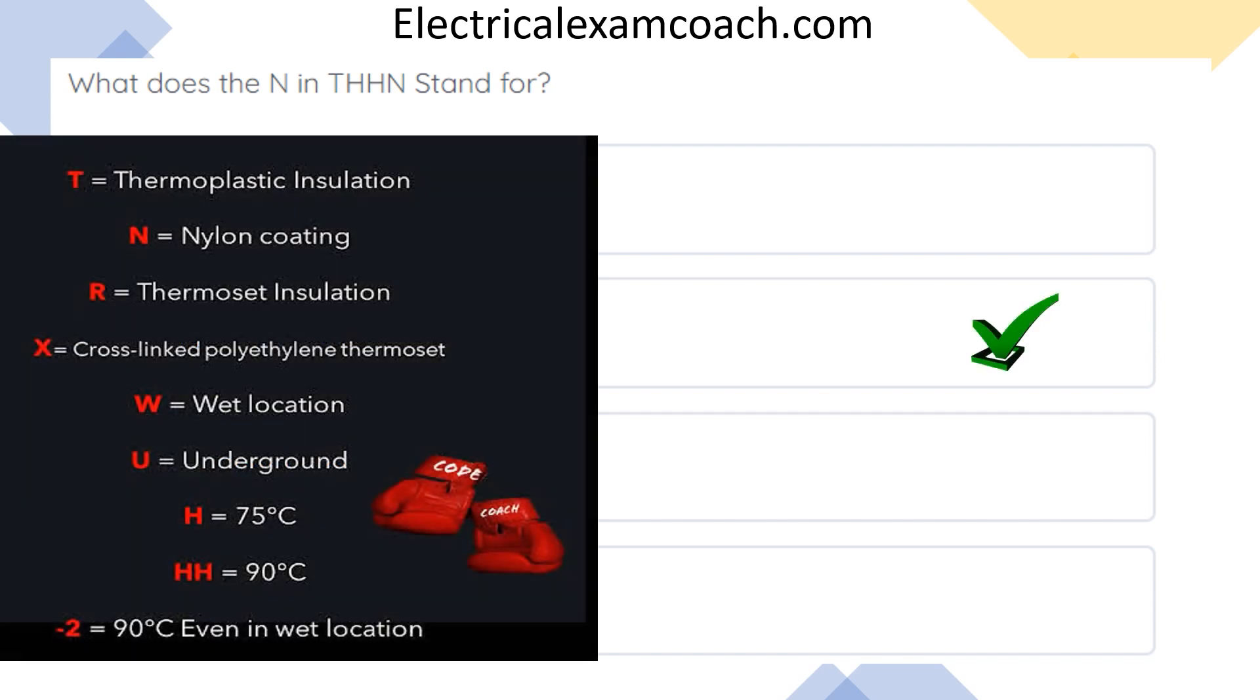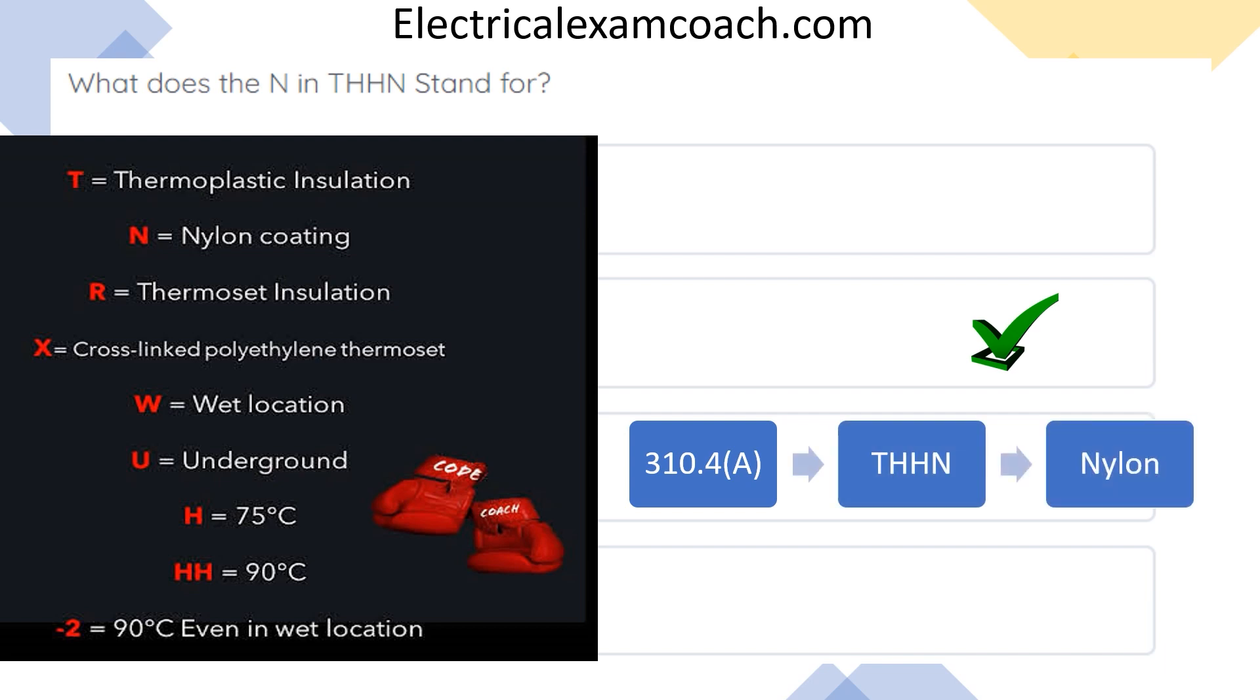So this is a picture that you can get at electricalcodecoach.com under free resources. And this is something that you can use to help you remember. This breaks them all down. How to find it in the code book is something that I actually want you to make a tab for. If you're allowed to make tabs in your state, if not, I just want you to go get familiar with the table. So you're going to head to table 310.4a and you're going to find THHN and then you would be able to find that it is equivalent to nylon coating. And when you get in there, you're going to learn all kinds of fun things about all the different types of wire, whether it's rated 75, 90, respectively, so on and so forth. I am the electrical code coach. Let's go ahead and get to it.